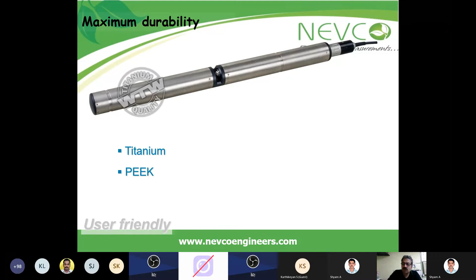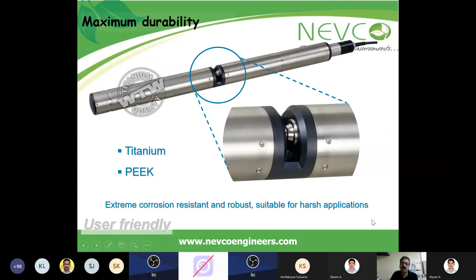This particular probe, whatever you are measuring, BOD, COD, is made up of titanium. So it will never have corrosion in its lifetime. You can see here, your sensor surface will always be clean. In this measurement, there is a xenon lamp. The light passes through the liquid, and it absorbs the wavelength of the liquid and correlates the BOD, COD, TSS, everything. So it has extreme corrosion resistance and is robust, suitable for harsh applications. In any application you can use this.